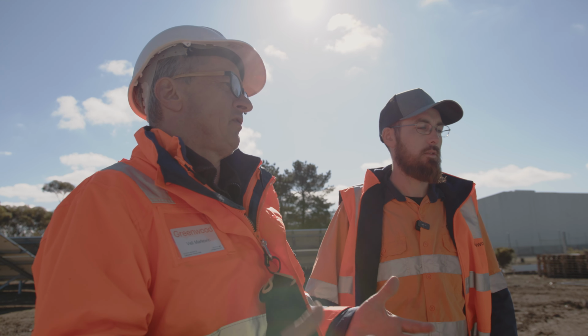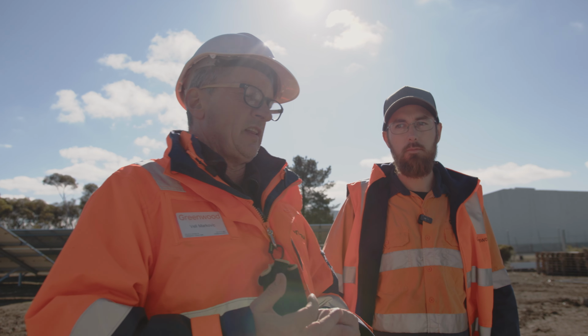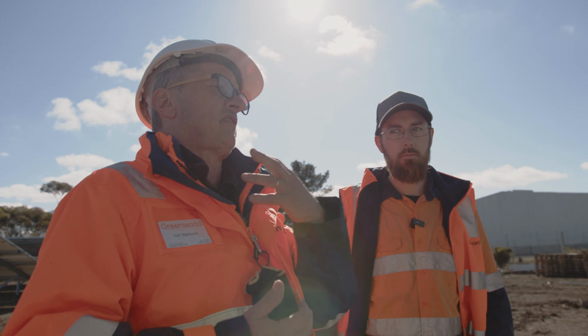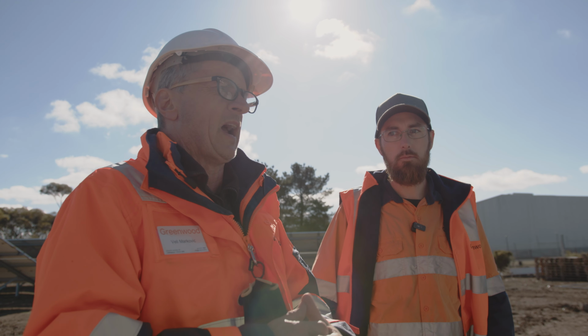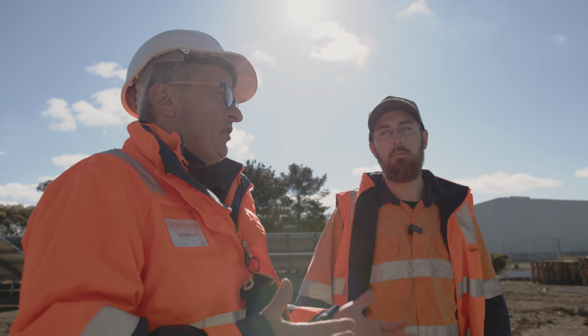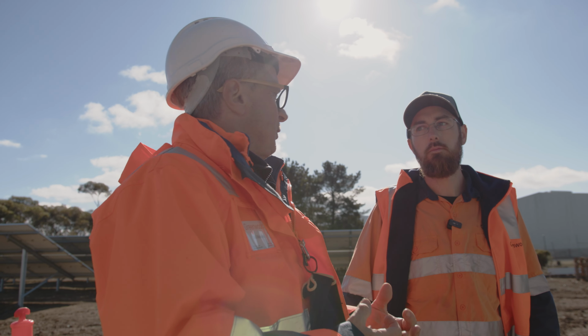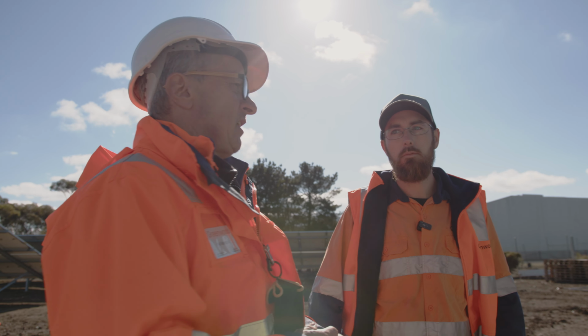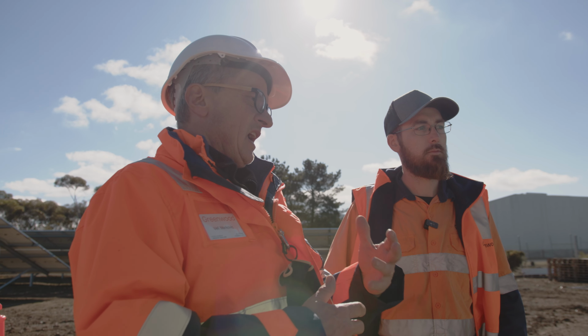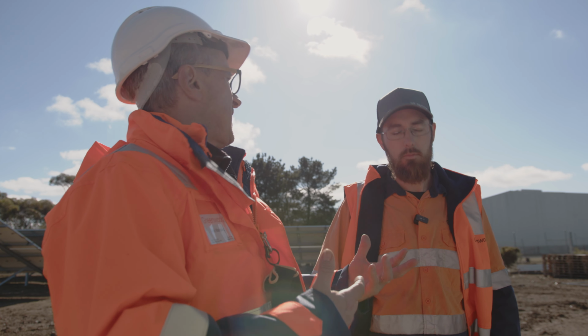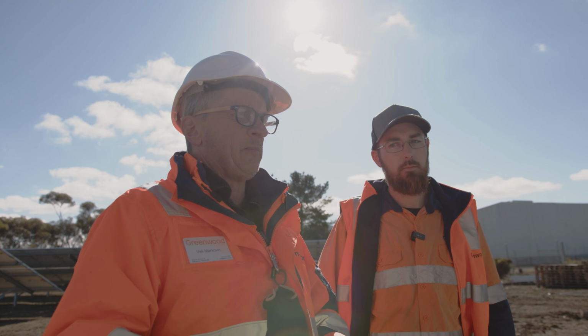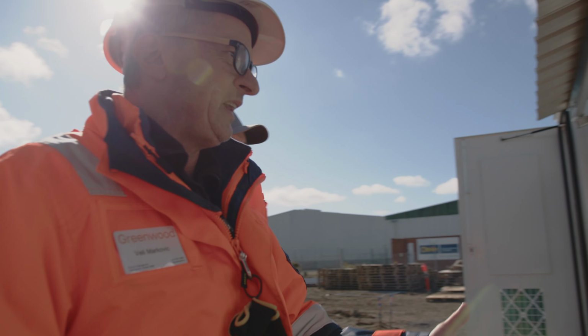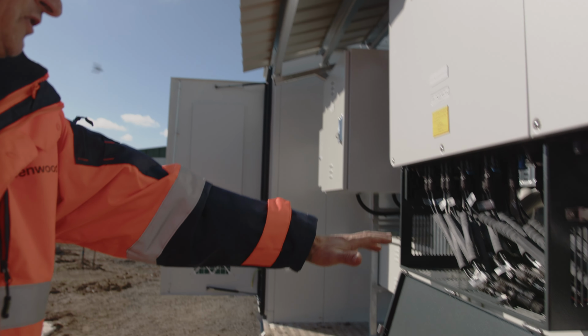We typically use 110 because it's less susceptible to temperature derating, and in a lot of cases on long runs you can end up using a thinner cable, especially when it comes to maxing out the cable tray and its capacity to hold cables. Now it's really interesting to see, back to the fusing here.